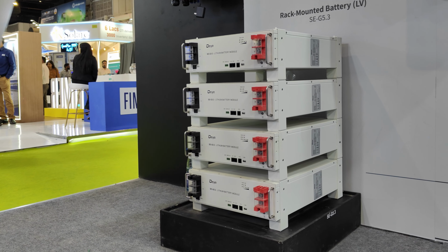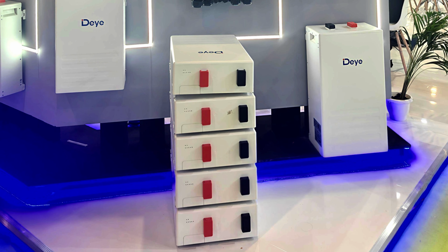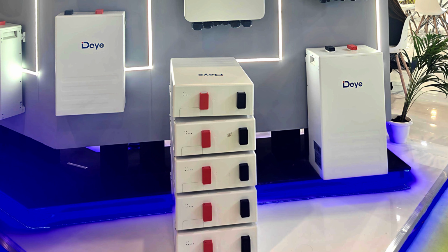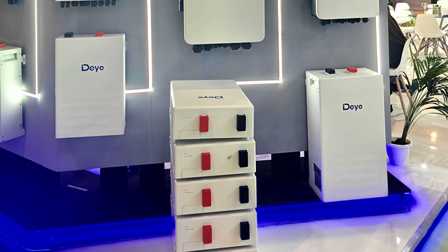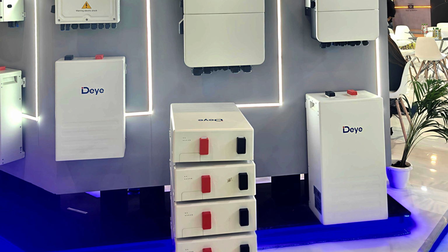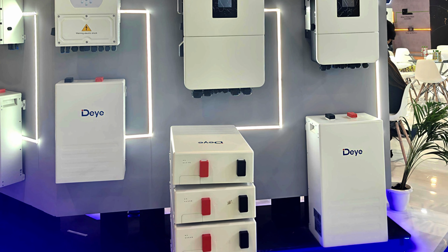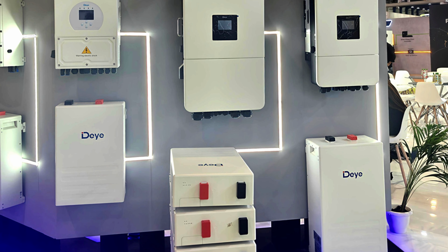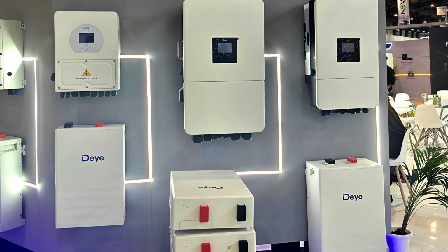And here, as much as possible, try to purchase the inverter and battery of the same brand so that you do not face problems at the time of service. Many times it happens that if your battery is giving low backup, the inverter brand may say that the battery has a problem. The battery brand may say that the inverter has more power loss. That is why you are not getting backup. Because if you have taken a transformer based inverter and also installed a lead acid battery, then the overall efficiency of this system remains around 60%. That means you charge the system with 1 unit and later you get only 0.6 unit back. And to avoid this, if you use a lithium battery plus hybrid plus transformerless inverter, then the efficiency of this system can be more than 90%. That means if you charge with 1 unit, then you will get 0.9 unit back.